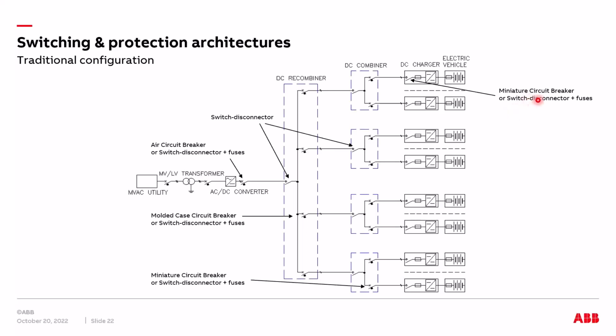We can also have a molded case circuit breaker and fuses installed inside our electric vehicles. Here we can have a double issue. First of all, if we have, for example, a fault at this point, we have a contribution, as I said, coming from all the other batteries installed in parallel. But we are not able to guarantee the selectivity between this circuit breaker, which is usually an air circuit breaker, and the internal fuses, in particular the so-called ultra-fast fuses. So we can have the shutdown of a complete system if we have a fault at this section, or for example at this section.